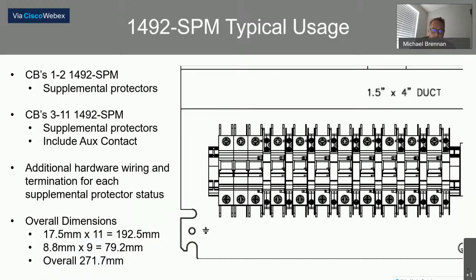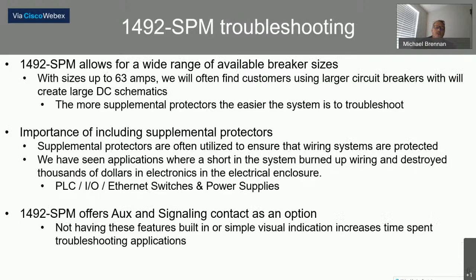So for 11 circuits, when we look at the overall dimensions, you're looking at about 271 millimeters. So it's small by comparison, but much larger than what you would see in a typical modular electronic circuit protection application. So, troubleshooting. One of the advantages of the SPM is it's available in a wide range of circuit breaker sizes, up to 63 amps. And what we will often see is our customers using a little bit larger circuit breakers with large DC schematics or DC circuits.